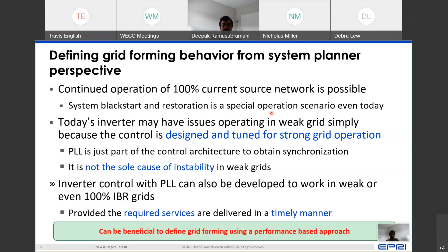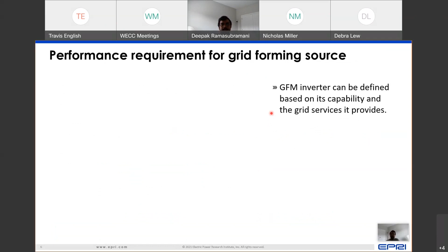Which means that inverter controls with phase lock loops can also be developed for 100% inverter systems, provided we tell the inverter-based resource what kind of services it needs to provide and in what time it should provide that service. And once it does that, it's all about providing the services for the system, and we can then get a stable operation. And in this regard, we can now flip and turn the definition of grid forming inverter to use a performance-based approach, wherein we specify that this grid forming source is defined purely based upon its capability and the grid services it provides, which can be operating with and without synchronous machines, operating with other inverters, providing positive contribution to load imbalance, voltage imbalance, fault ride-through, while meeting its equipment limits and while meeting standard acceptable metrics.